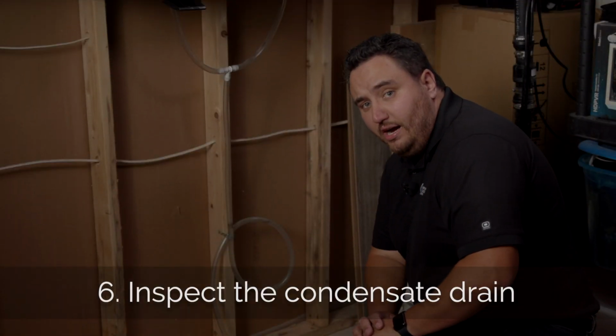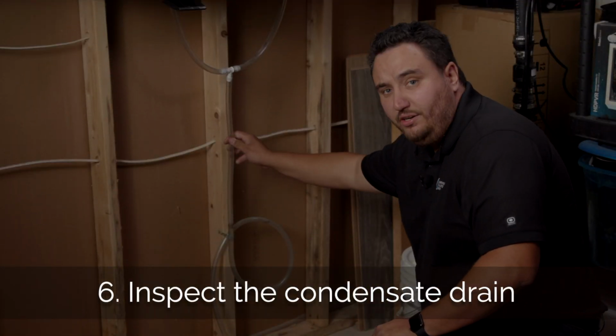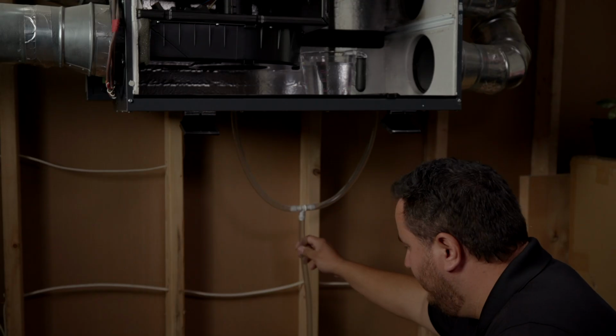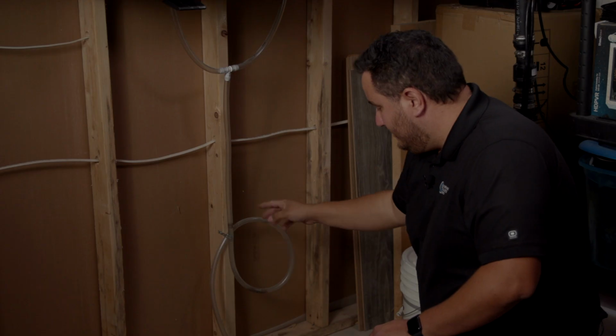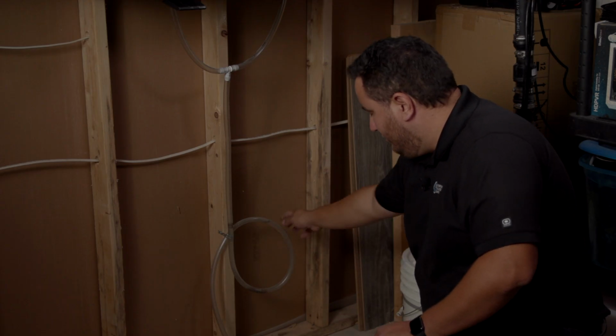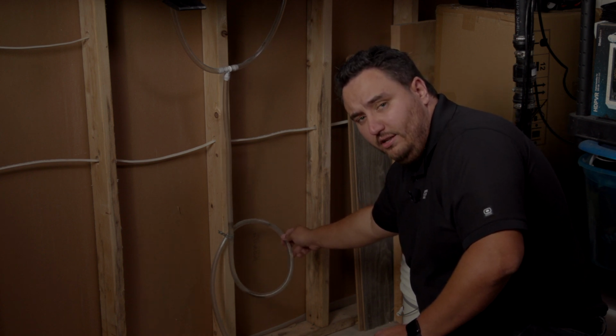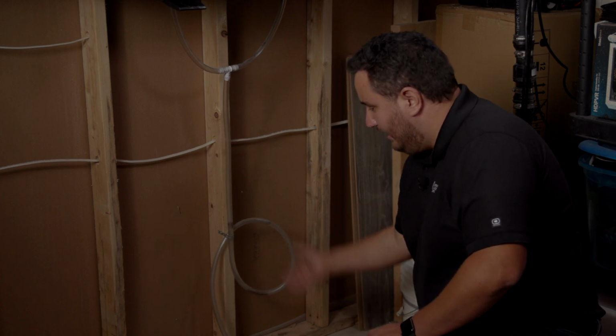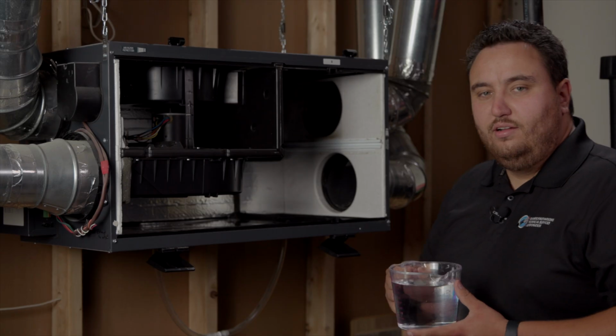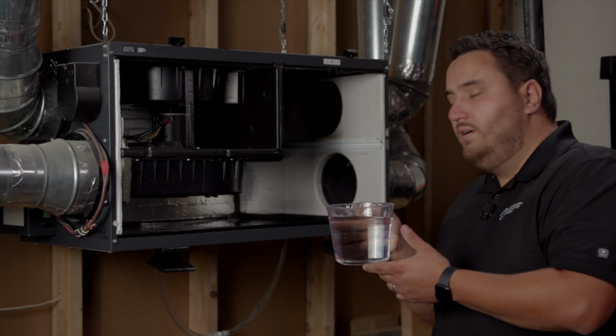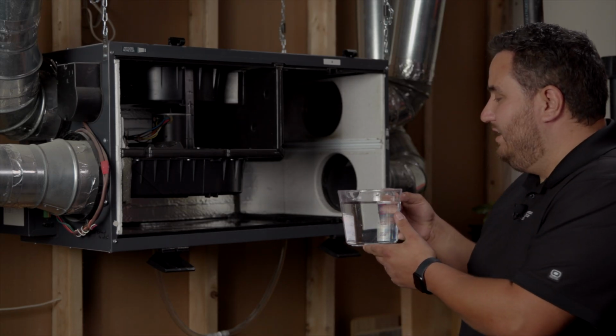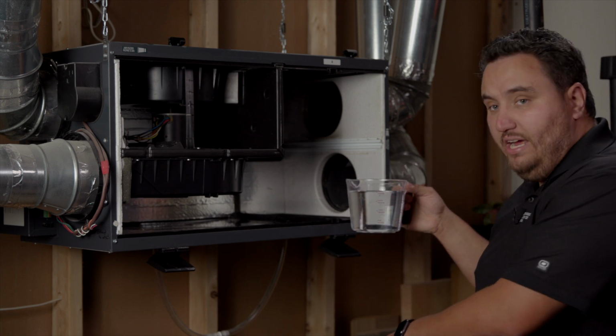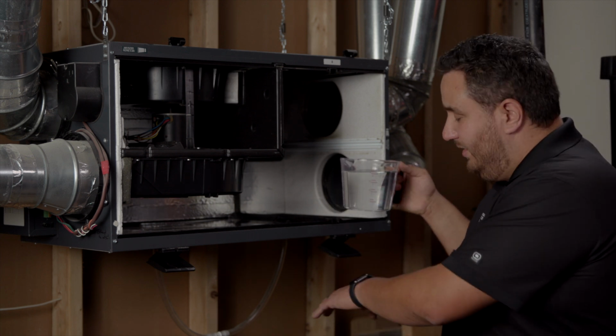Next, we want to inspect the condensate drain. This is the clear tubing that comes out of the bottom of the HRV. It gets rid of any condensation and drains it out. You always want to make sure you have a trap in the condensate drain so you don't get sewer gases coming back up into the unit. We're going to pour about 2 liters of warm water inside the drain pan of the HRV, making sure it drains down. If there's any blockages, we can flush them out.